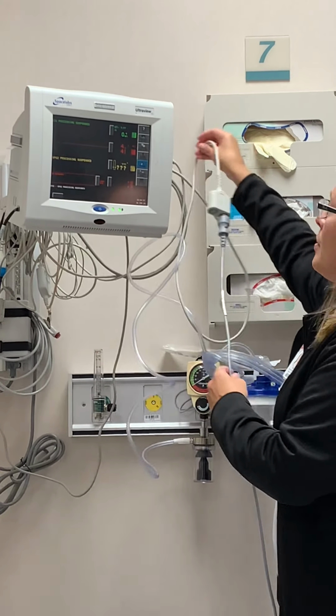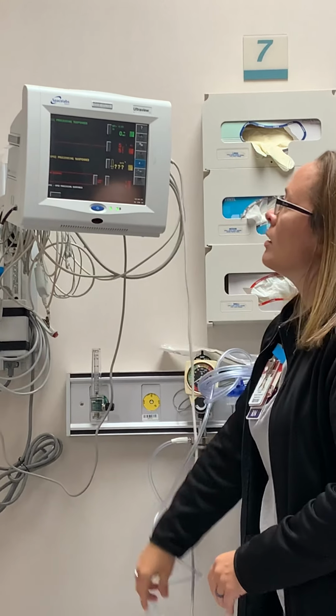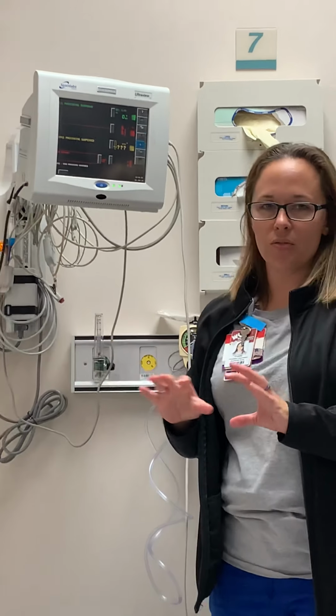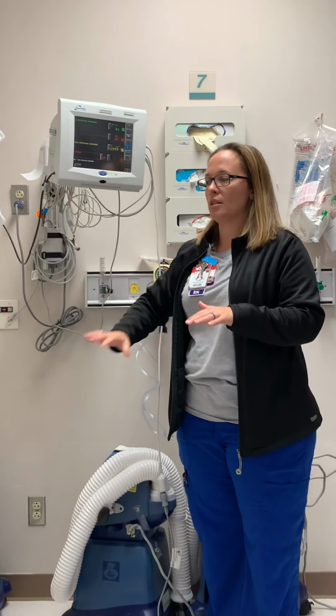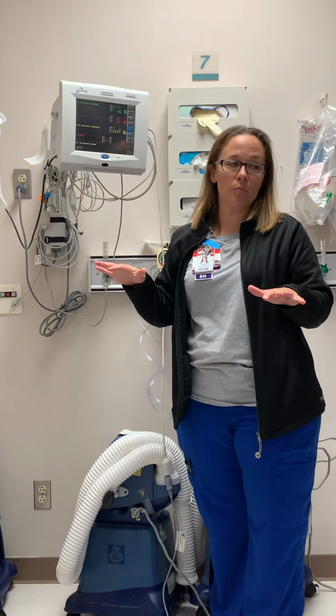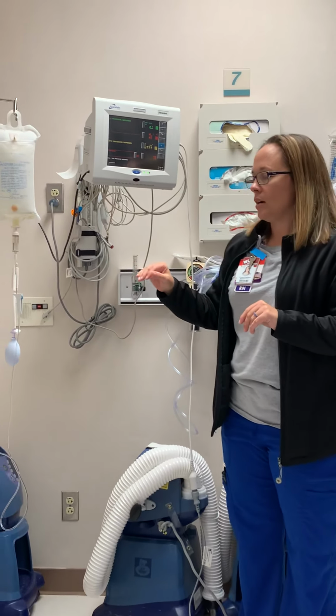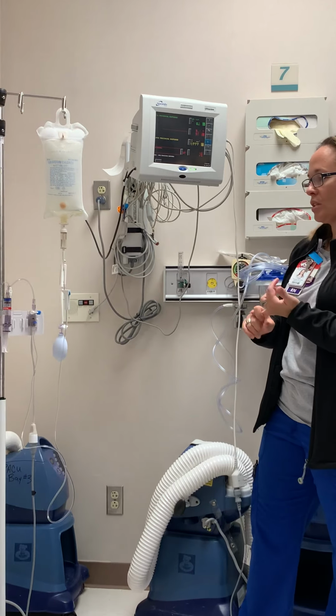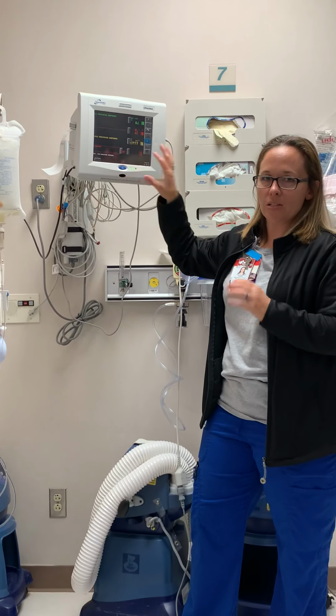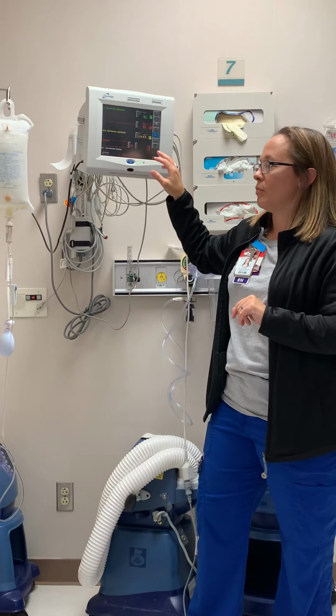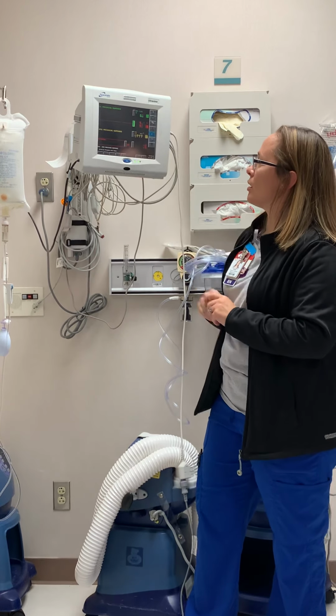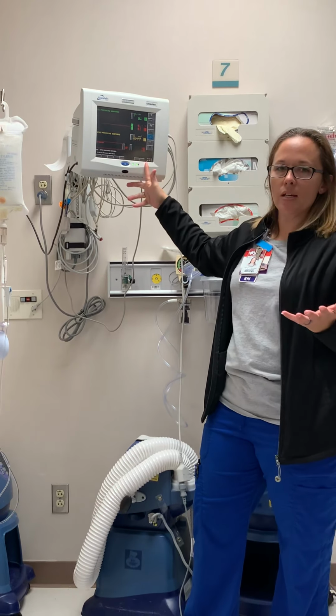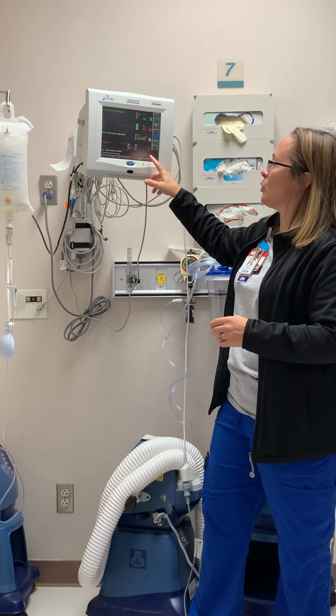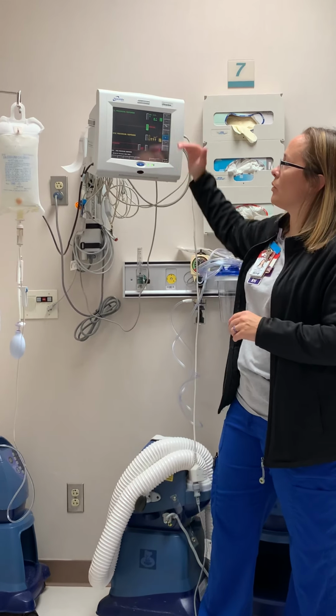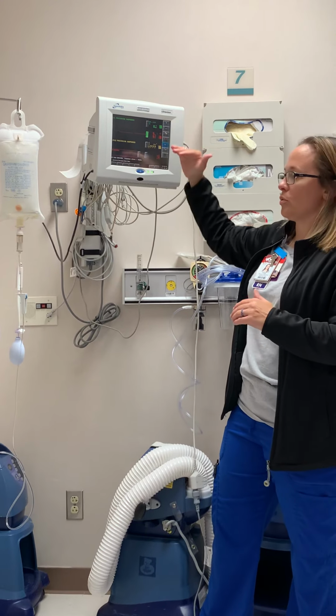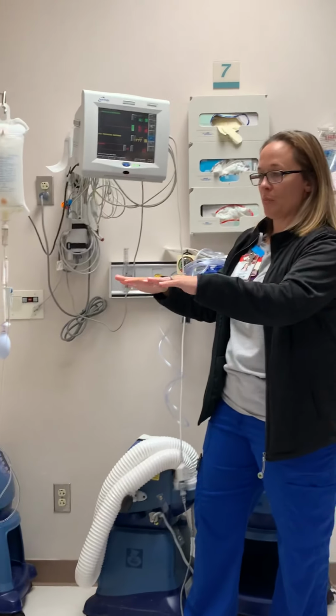Once you get that set up, then you have to zero the line itself. Zeroing the line itself means basically that you're equalizing the atmospheric pressure to the patient's pressure of the line. So the way to do that, there's 2 things you got to do. You got to zero the monitor. That's the first thing that you do when you get it set up. So you want to hit your art line, and there's a 0 button. It's very easy, self-explanatory in a sense. But you want to hit that line to zero it out, and what it's going to do is it's going to equalize the pressure that it's getting from the patient.